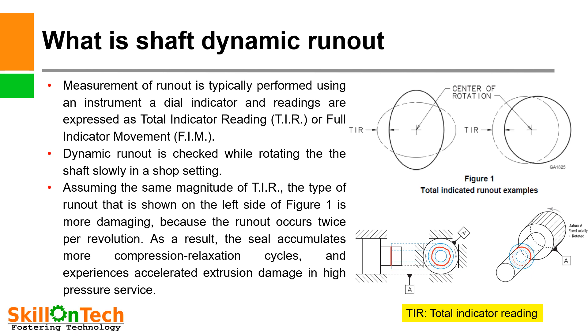Shaft dynamic runout. Measurement of runout is typically performed using a dial indicator, and readings are expressed as Total Indicator Reading (TIR) or Full Indicator Movement. A dial indicator has 1 mm of movement in a circle divided into 100 divisions, so one division equals 1/100 mm. Here in this slide you can see Total Indicator Runout examples. TIR is a deviation that will be shown on the dial gauge.